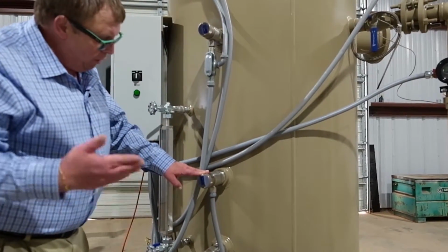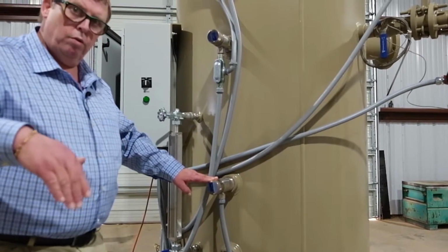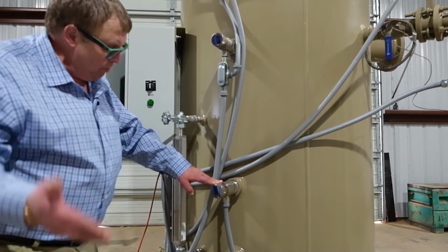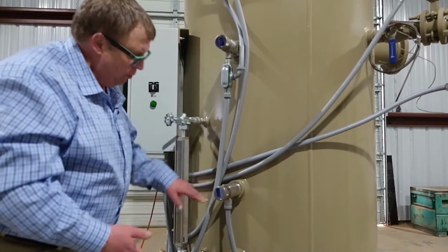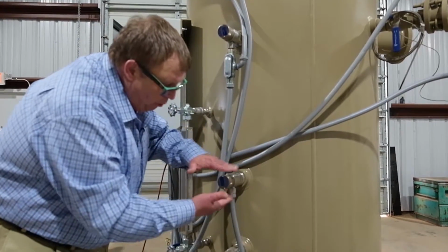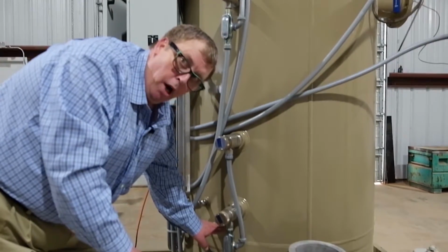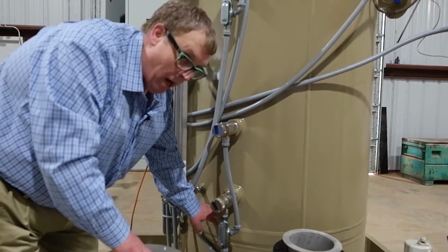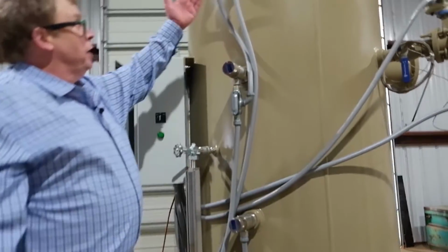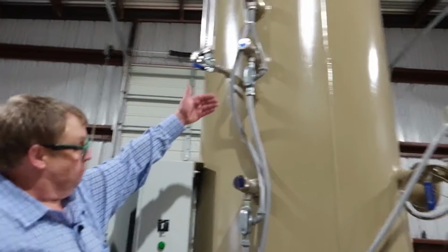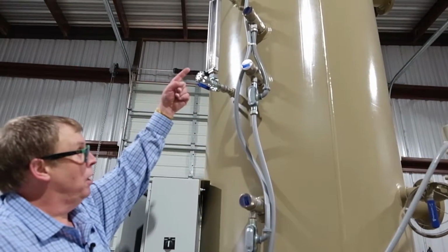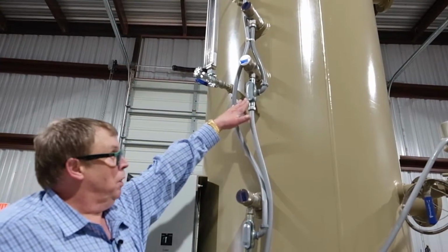Pump kicks on, pumps off this distance of liquid, pump turns off. That's important because we're not using it like a snap control, or some folks may use a throttle control, but we want to evacuate that much liquid and also leave liquid in the bottom section so that we don't lose prime. Same thing's happening above. You have your pump actuated, pump on, pumps down the liquids, pump off.